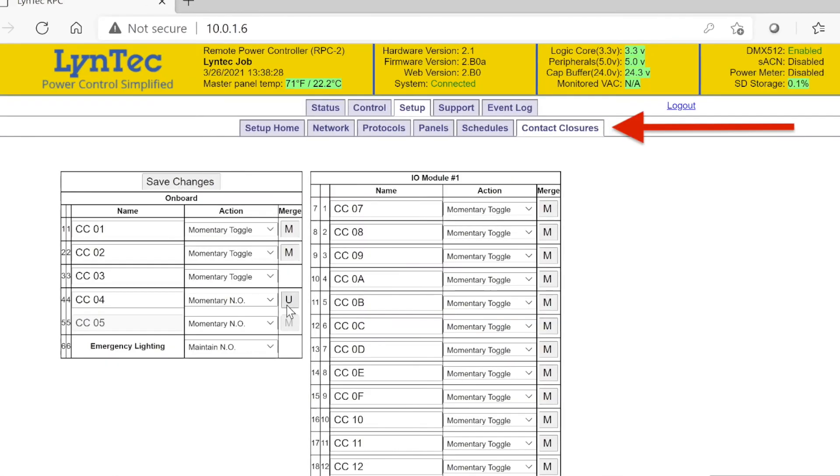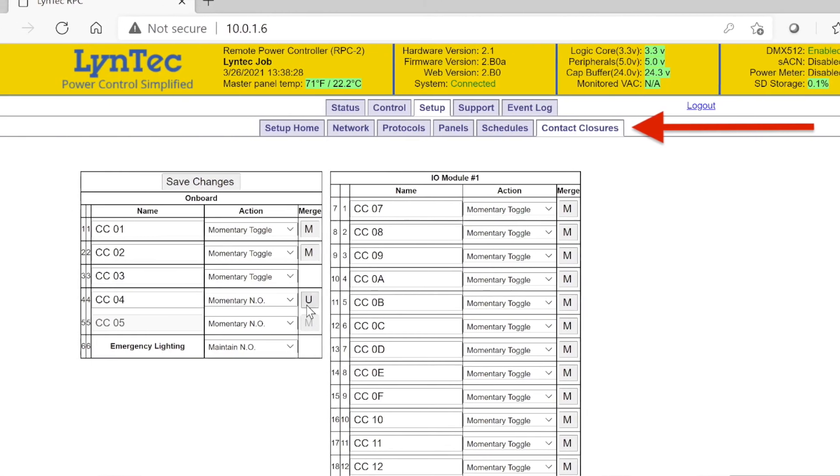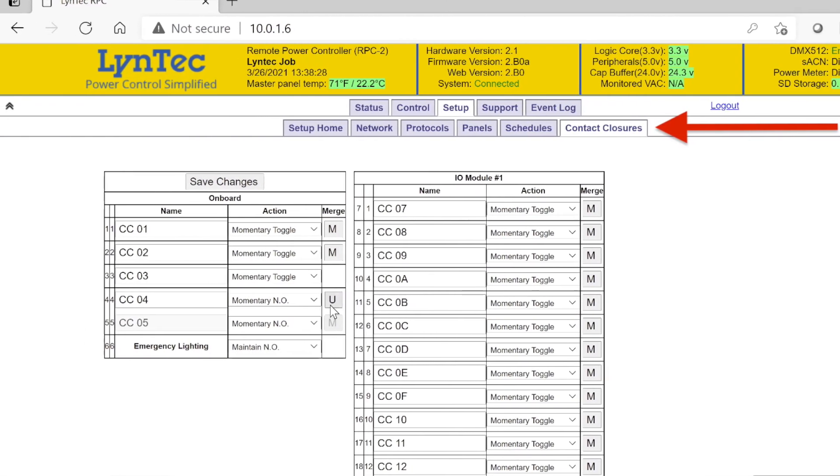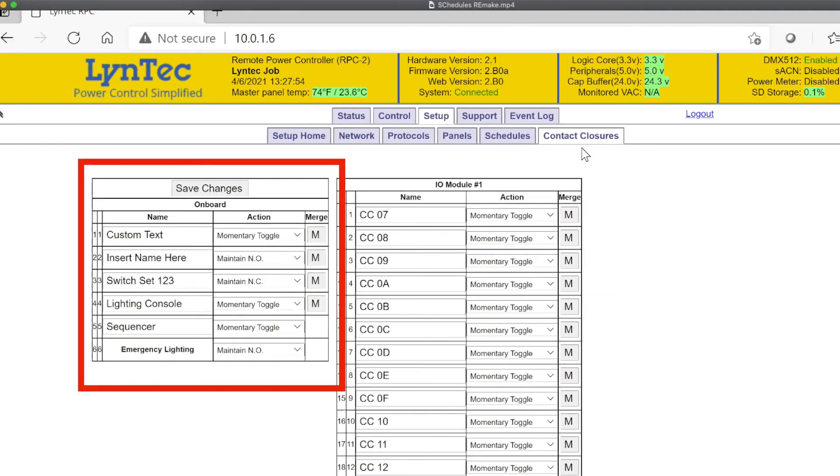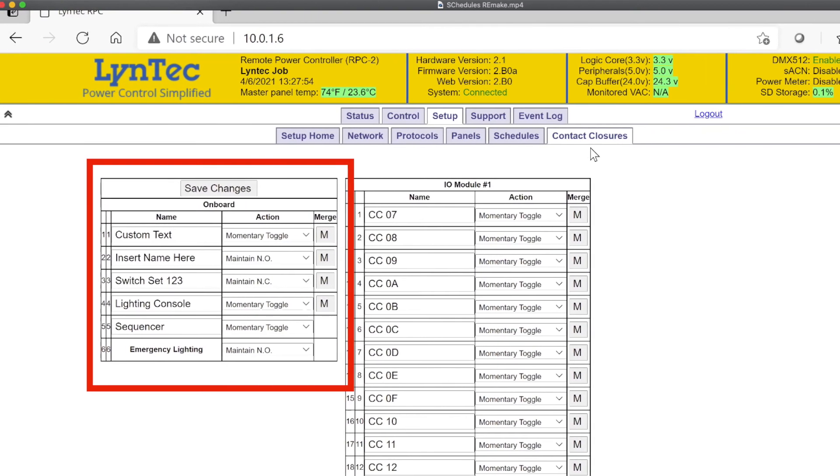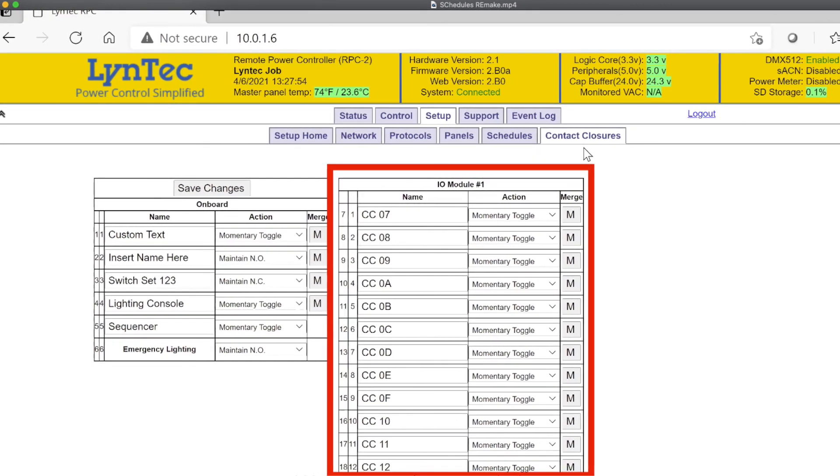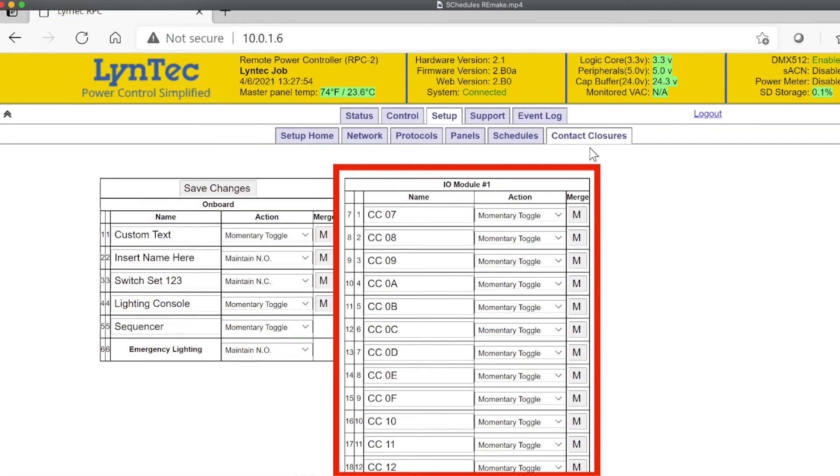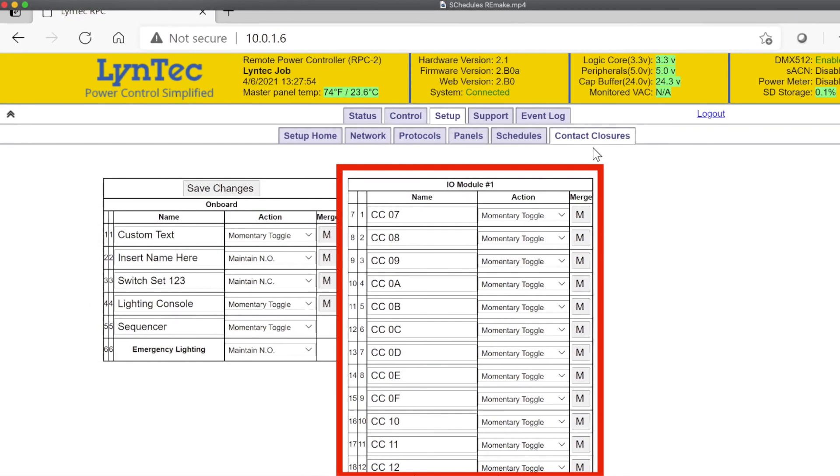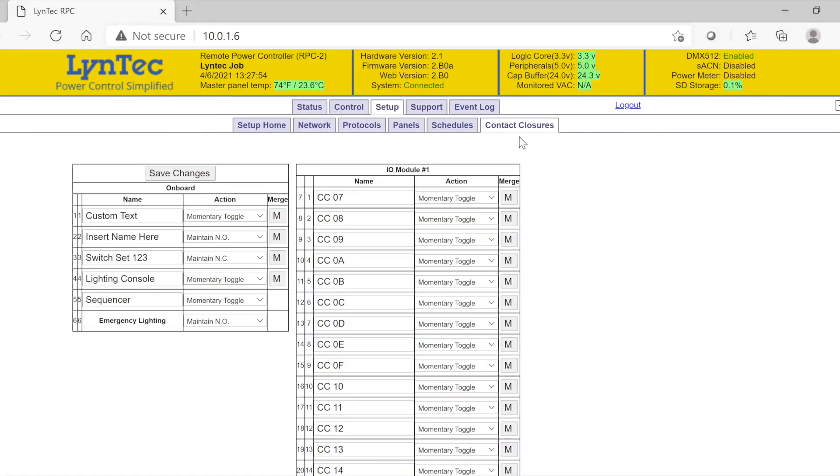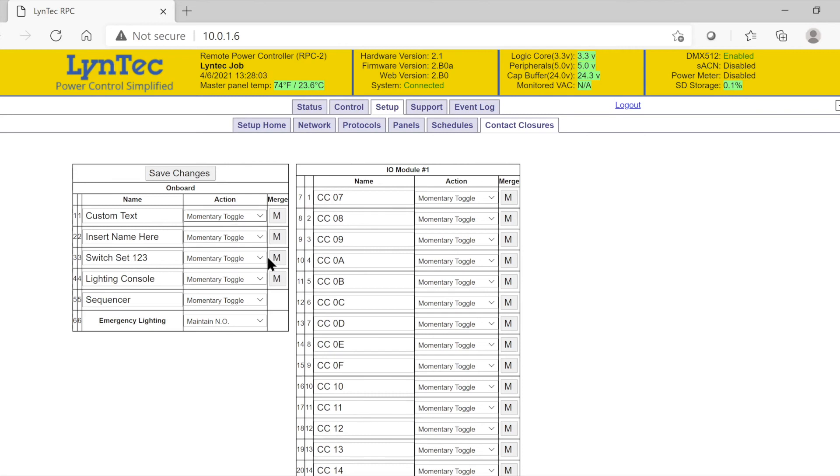The last tab we will review is contact closures. Each LCP controller comes standard with six contact ports. If any optional accessories like an IO board are installed, this is where their functionality can be programmed. LynTec programming allows for contacts to serve as normally open, normally closed, or as momentary toggle. This is where we can also merge adjacent ports together as well.